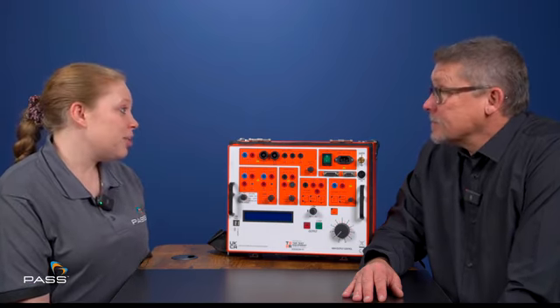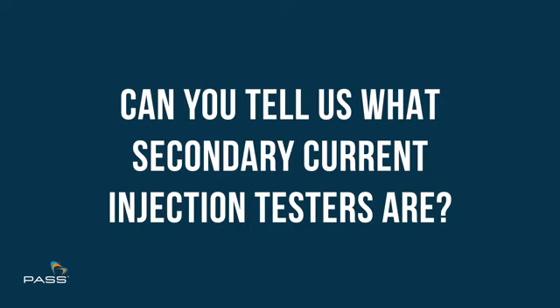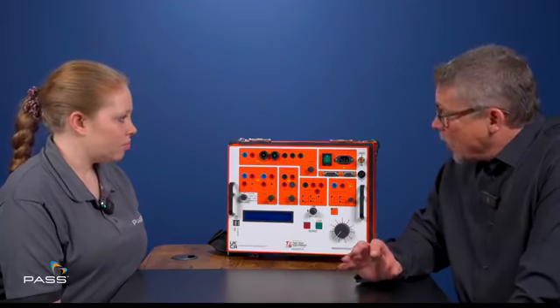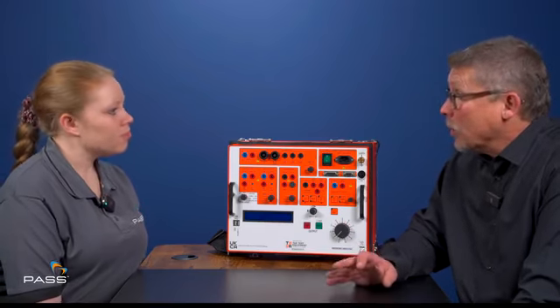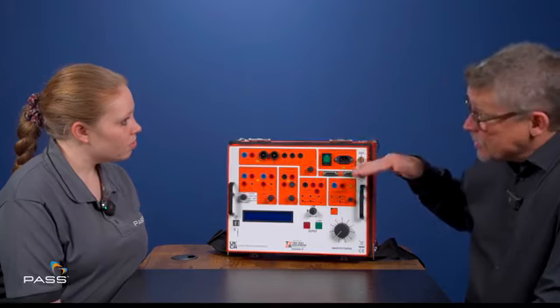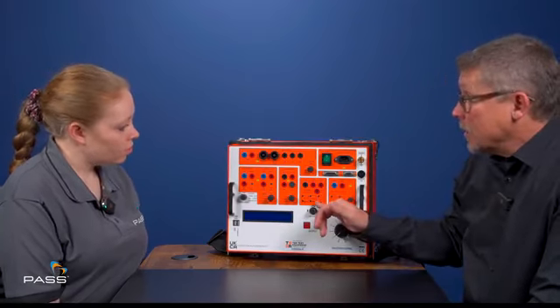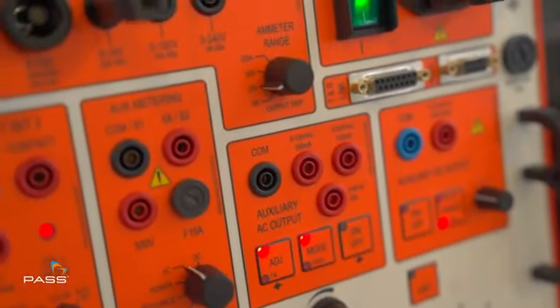So before we get into talking about the T&R 200ADM-P, please could you give us an overview of what secondary current injection testers are? Yeah, it's very, very simple, really. Secondary injection test sets, well, all injection test sets, by the name suggesting, are current injection units. They will inject a controlled current into either a relay or a circuit to test that relay or circuit. Most units operate on the basis of just one current output. And what makes this unit a little bit different, as we'll see as we go through, is we have a secondary channel, and that will give us, again, a secondary current as well as the main current. So that's where the P comes into it. And the P literally stands for phase shifting.